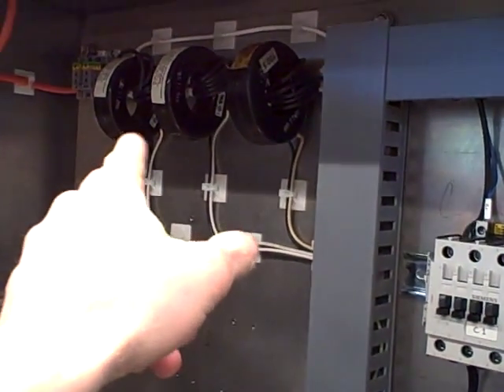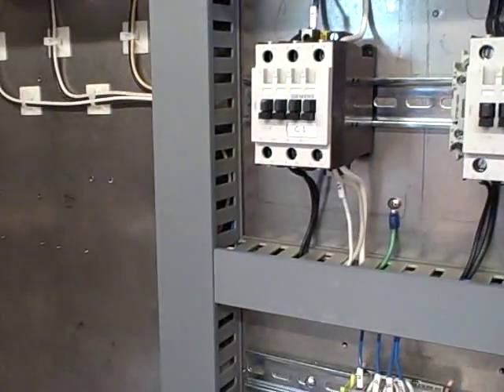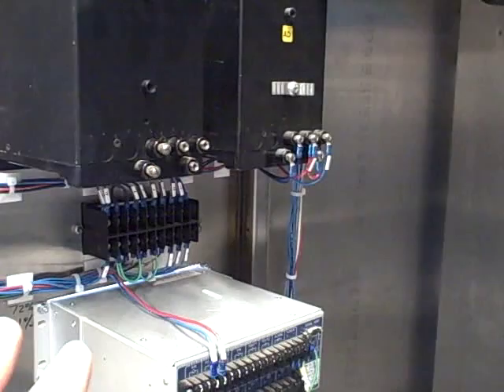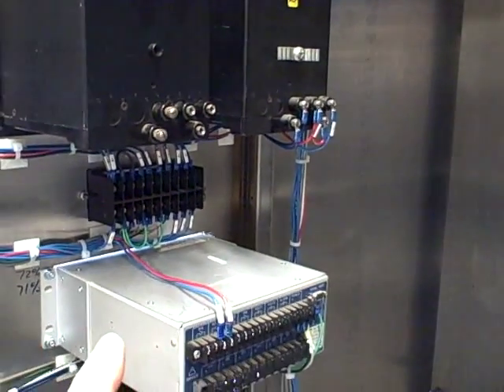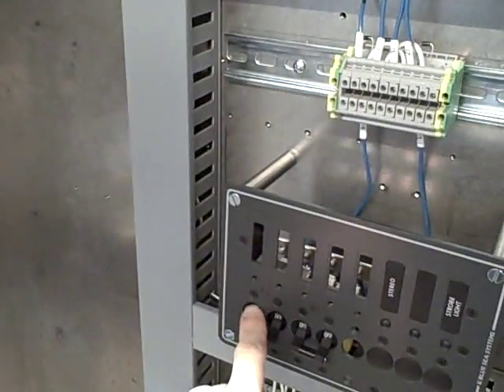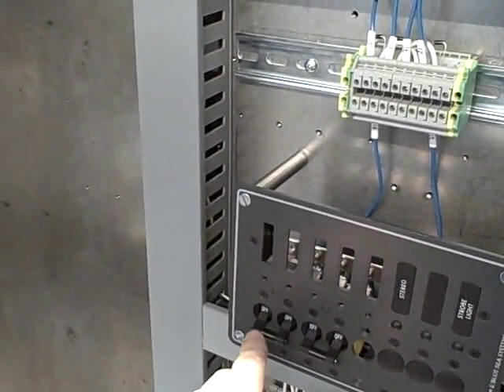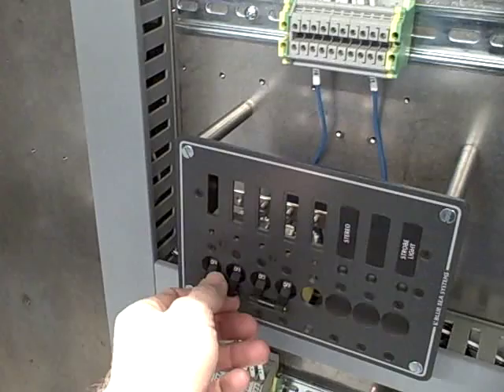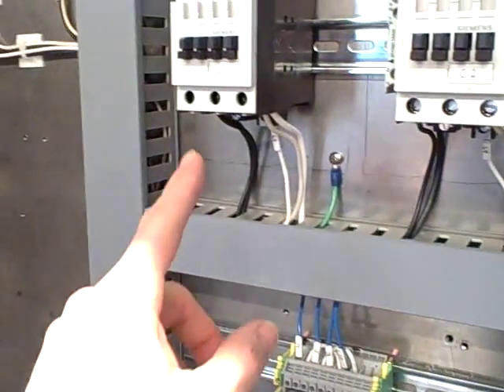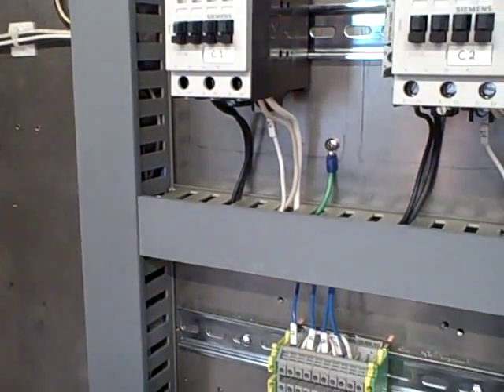We're going to measure the load current with the current transformer up here. If the protective relays detect an overcurrent condition, they'll send a trip signal down to this relatively small circuit breaker which will then trip and de-energize the contactor.